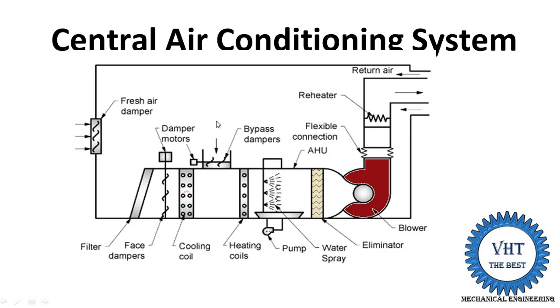Here the heating coil is provided, and here is a bypass damper. This cooling coil is for the cooling and dehumidification process. The heating coil is for heating — an electric heater or similar device is installed. This is the water spray for humidification purposes. There are also eliminators and a blower. This is the duct from where the air is supplied to the rooms.